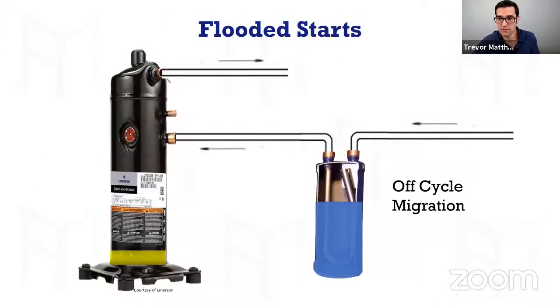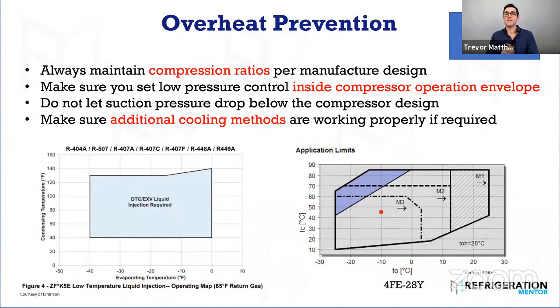And the next thing, overheat prevention. Always maintain that compression ratio. Every compressor is going to have an operation envelope. So down on the left-hand side, you can see this one's a ZF scroll compressor from Copeland. That's the operation envelope of this one with those specific refrigerants, because it's going to change per refrigerant. And then it's going to tell you if you need injection or no injection or head cooling fan.